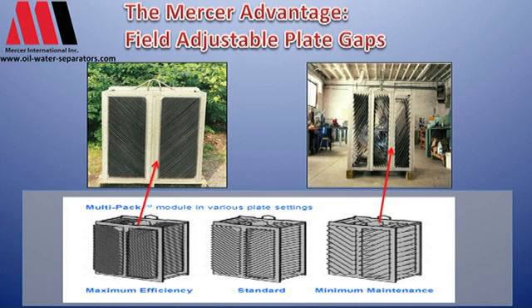The other thing that we've seen done in the field—you have to put a little time and energy to do this—but if you keep track of the fouling in a plate pack system, you can actually find areas where more solids are going to be. For instance, typically near the very bottom of the pack or up near a sludge layer on the top.